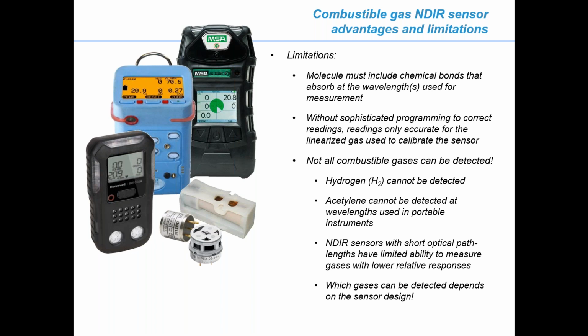Typically, what we're going to use is a highly reliable substance-specific electrochemical sensor to detect the hydrogen. We're not going to infer the presence of hydrogen by using a bad CO sensor that happens to have a relative response to hydrogen as well as to carbon monoxide. Our approach is a little bit more accurate than that, and we're going to depend on that electrochemical sensor. Another gas of interest is acetylene. If LEL range measurement of acetylene is what you need, then you should stick with a catalytic LEL sensor. In our products, you are welcome to include both a catalytic LEL sensor and an IR LEL sensor in the same instrument. We don't rule that out. That's one approach.